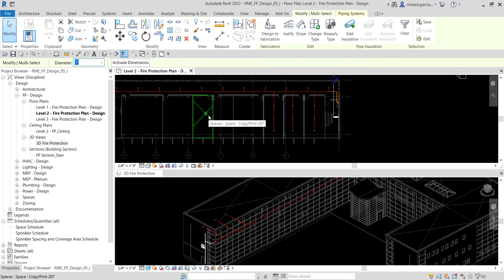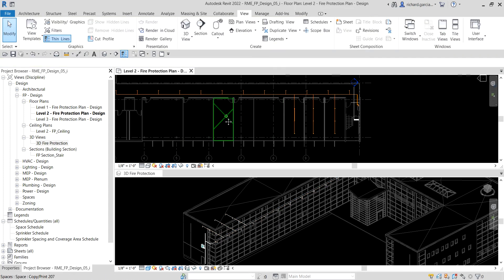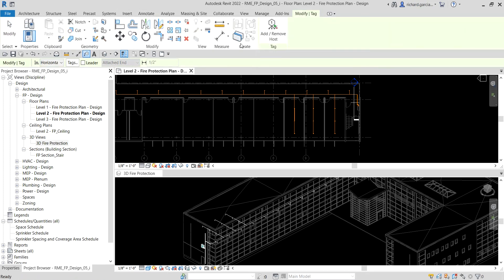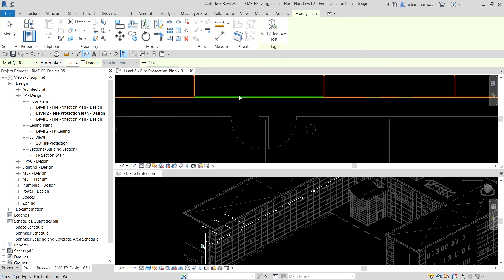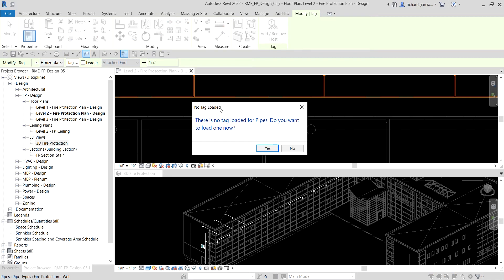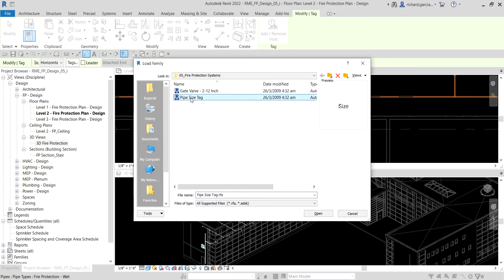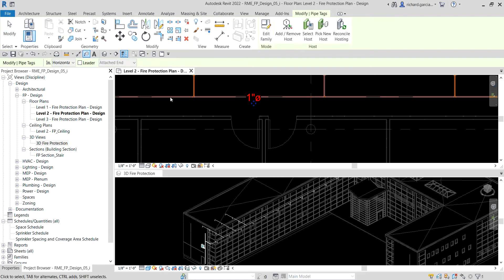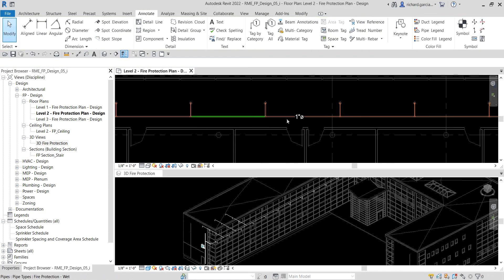All selected piping is now one-inch diameter. To verify, I'll tag the model. From the Annotate tab I select Tag by Category and click one of the pipes. A dialog box appears saying no tag is loaded, so I select Yes to load one. I select the pipe size tag and click Open, and as you can see it now shows one-inch diameter.